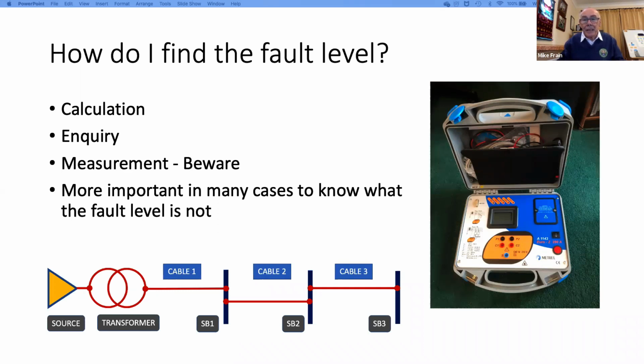So that is the case whether it's for calculations to IEEE 1584 or the German box test DGUV that I referred to earlier, or even PPE if you want to use the shortcuts from NFPA 70E standards table. Still need the fault current and the disconnection time in that case in order to come up with PPE.